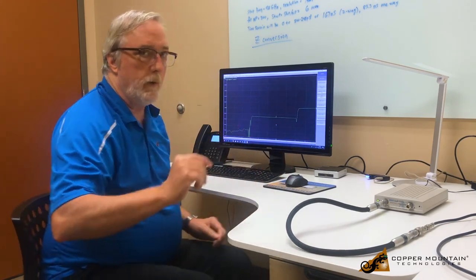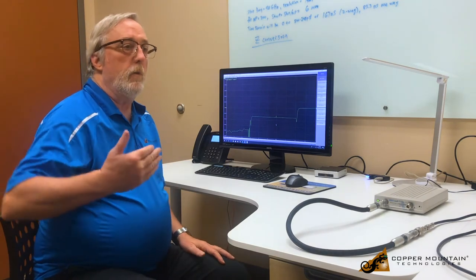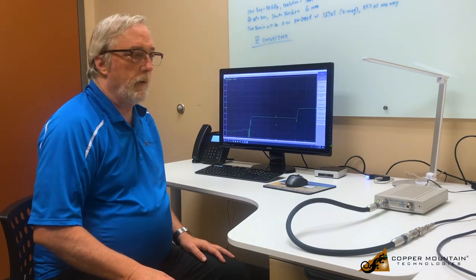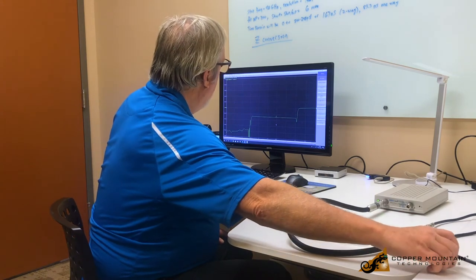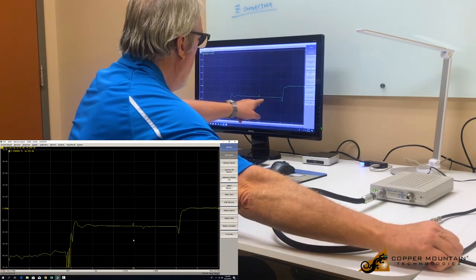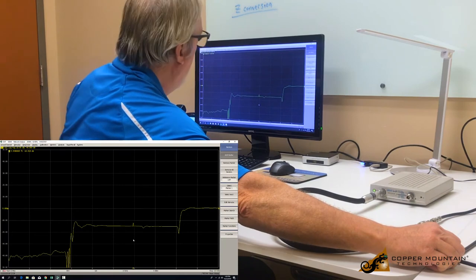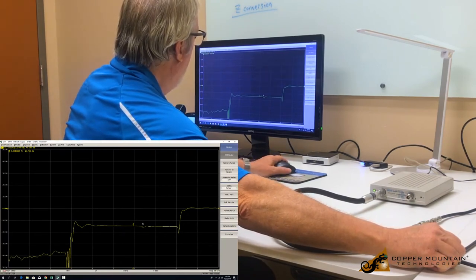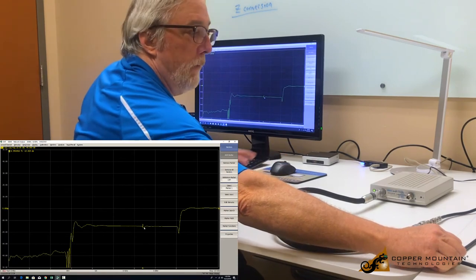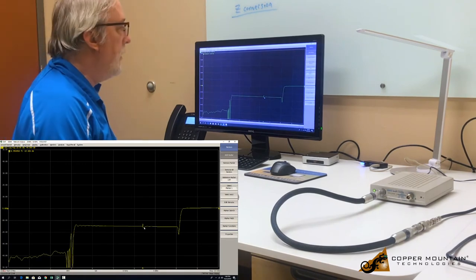This is giving us a good view through this entire cable. If this had been a cable going up to a tower to, say, a land mobile radio antenna, we'd be able to analyze the return loss of that cable all the way up the tower, and we'd be able to see if there was water in the coax or some other failure. I can introduce a kink in the 75-ohm cable, and you can see it right here. There's a defect I'm creating by crimping the cable, and I can locate it in distance with a marker. It is 6.4 feet down this entire cable system, which would make it very easy to find if it were a defect in a wall or some other hard-to-reach place.